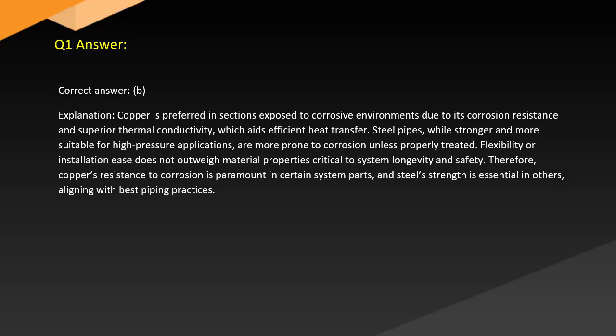Copper is preferred in sections exposed to corrosive environments due to its corrosion resistance and superior thermal conductivity, which aids efficient heat transfer. Steel pipes, while stronger and more suitable for high-pressure applications, are more prone to corrosion unless properly treated. Flexibility or installation ease does not outweigh material properties critical to system longevity and safety. Therefore, resistance to corrosion is paramount in certain system parts and steel's strength is essential in others, aligning with best piping practices.